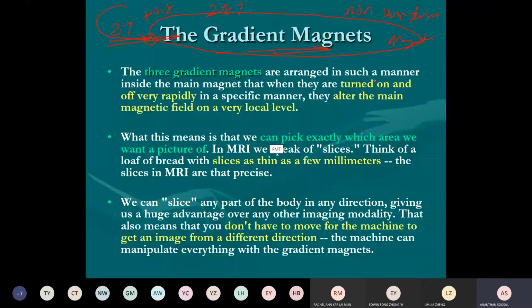Three gradient magnets are arranged in such a manner inside the magnet, and they turn on and off very rapidly. They alter the main magnetic field on a very local level. The magnetic field is changed, so we can pick exactly which area we want the picture of. The MRI picks slices. Think of a loaf of bread with a slice as thin as a few millimeters. We can slice any part of the body if you like, giving a huge advantage to the MRI. Okay.